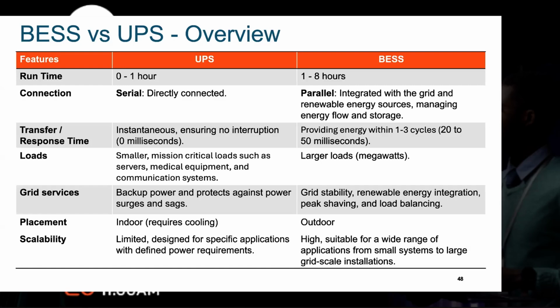Even in climates like Europe where you have consistent power supply, they still operate UPSs, because the power must be clean and available without any glitch for critical facilities like servers and medical equipment during surgeries. UPSs handle smaller loads for mission-critical facilities, but BESS allows larger loads in megawatts. That's part of the difference between the two solutions.